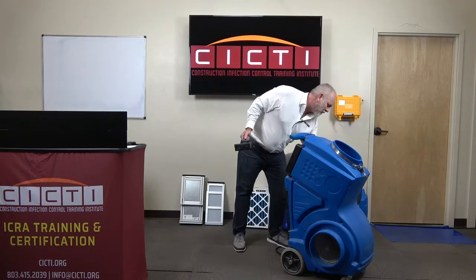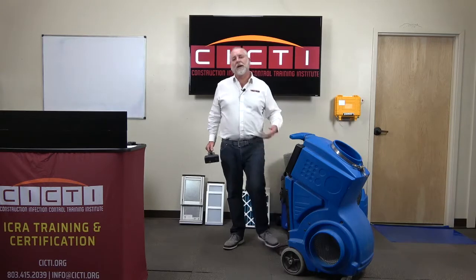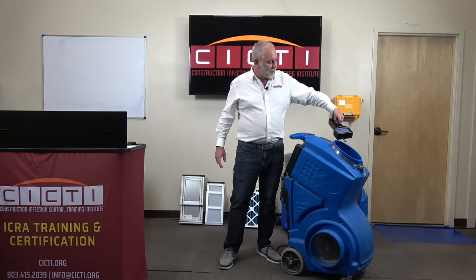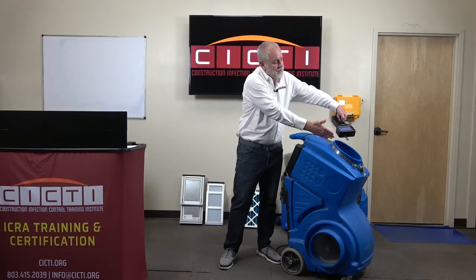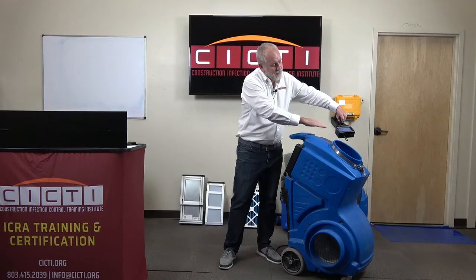So I'm going to power up the device and let that fan motor assembly get up to full RPMs. You may be able to hear that in my microphone, I'm not sure. But now I'm going to take a reading perpendicular to airflow here. So I've started my sample. You'll notice how I'm holding the silver probe. It's perpendicular. The airflow is coming in this direction, but I've got my probe pointed in this direction.